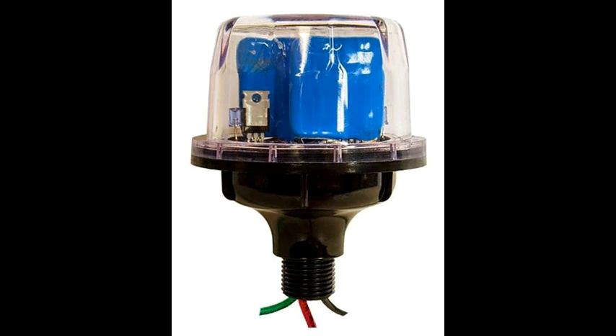Surge capacitors act extremely fast and catch those high voltage spikes of an AC line. For the best defense and lightning protection, combine a DC surge arrestor on the array side and a surge arrestor and capacitor on the AC side. Surge protectors should be installed at both ends of any long wire run connected to any part of your system, including AC lines from the inverter. Arrestors are made for various voltages for both AC and DC, so be sure to use the appropriate arrestor for your application.